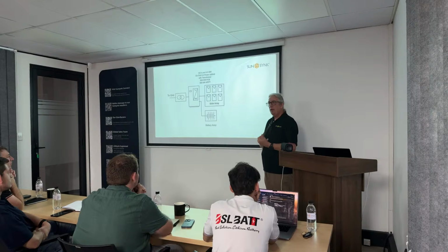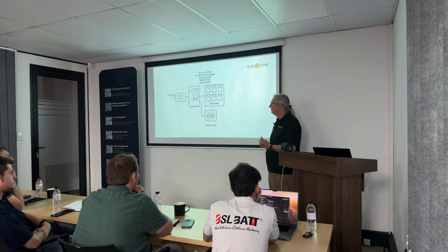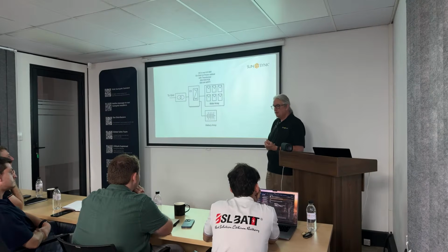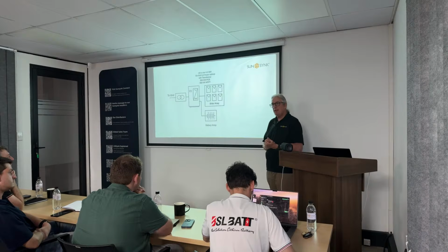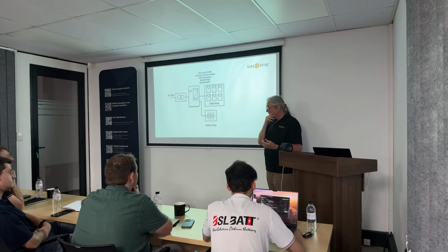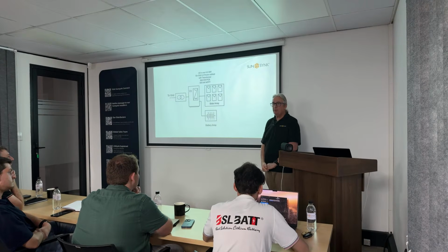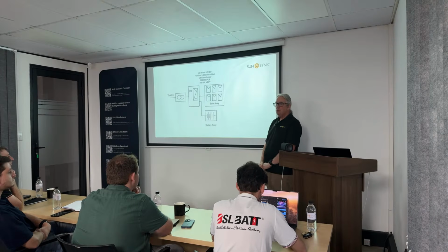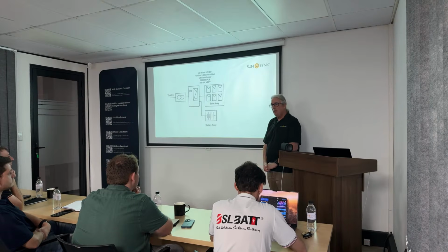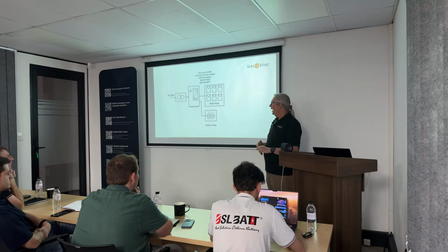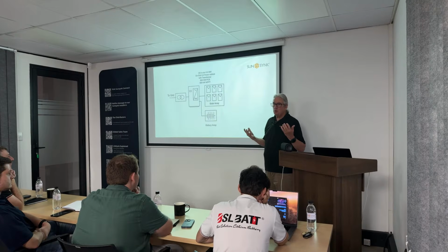Generally in South Africa, you don't need a transformer to couple it. The reason why a lot of inverters tend to use transformers is that on the bigger stuff, they output in delta format. So if you output on the inverter, on the PCS, you've got delta, you have to use a transformer to convert it to star, or Y connection, whatever you call it, because you haven't got a neutral.